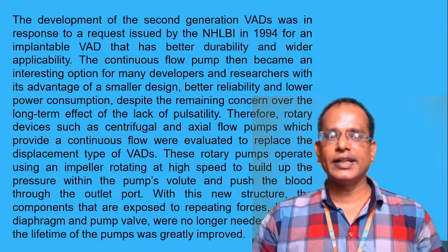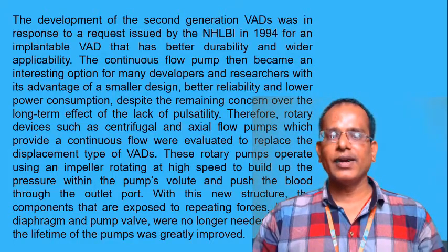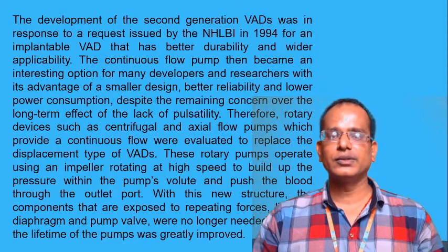Therefore, rotary devices such as centrifugal and axial flow pumps can provide a continuous flow rate and were evaluated to replace the displacement type of VAD. These rotary pumps operate using an impeller rotating at high speed to build up the pressure within the pump's volute and push the blood through the outlet port.